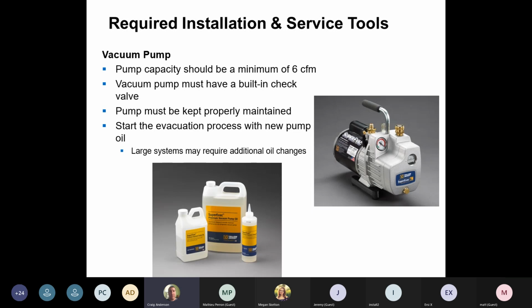So what happens to the oil is you're taking the moisture out of the system, it's going in the oil. So if your oil has too much moisture, it's going to take you a long time to pull a vacuum, or it's not going to pull a vacuum. So that could give you an idea of saying, okay, well, I'm not pulling a vacuum. Maybe I have a leak. No, maybe it's the oil that's in your vacuum. It's diluted so much that it can't take any more moisture. So make sure you're changing the oil frequently on it.